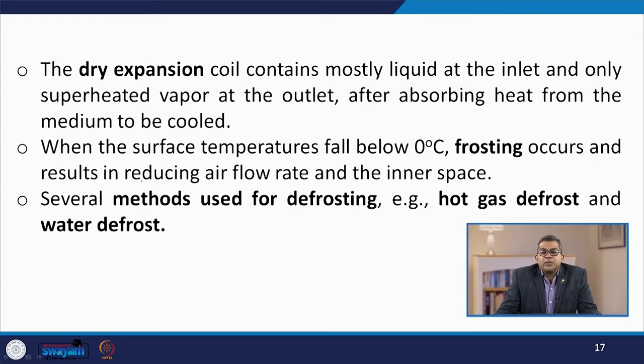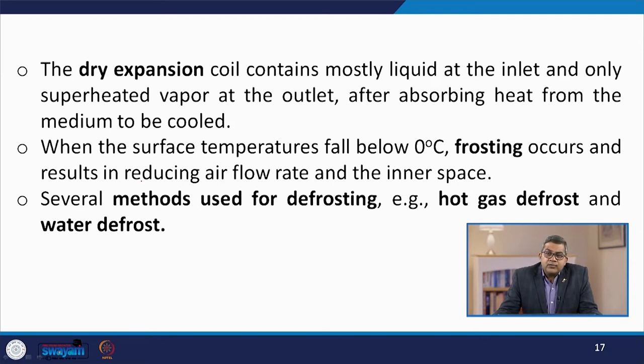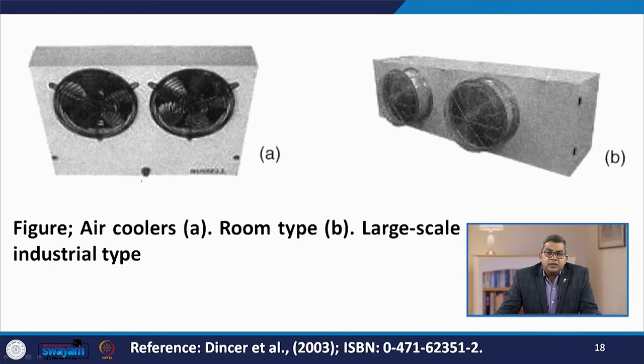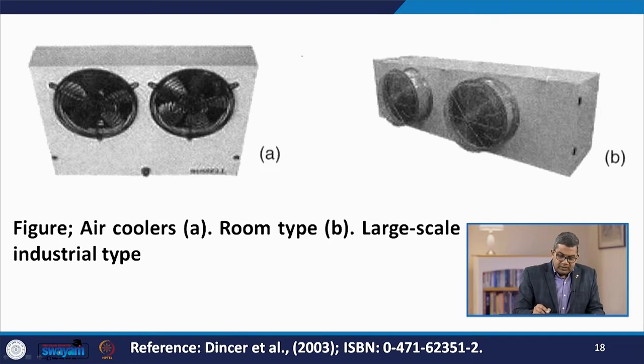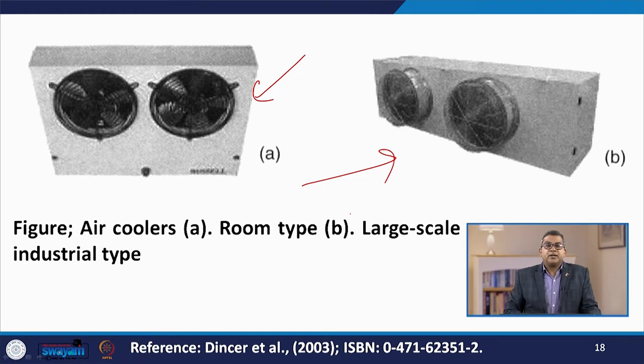Flooded type evaporators are not preferable in practical applications because they require large amounts of refrigerant. A dry coil requires only a small amount of refrigerant, reducing the cost of refrigerant charges. The dry expansion coil contains mostly liquid at the inlet and only superheated vapor at the outlet after absorbing heat from the medium. When the surface temperature falls below 0°C, frosting occurs, reducing airflow rate. Several methods are used for defrosting, like hot gas defrosters and water defrost. Here you can see room type and large scale industrial type air coolers.